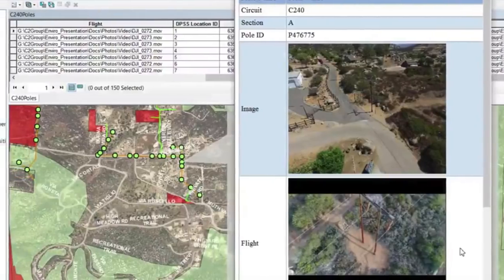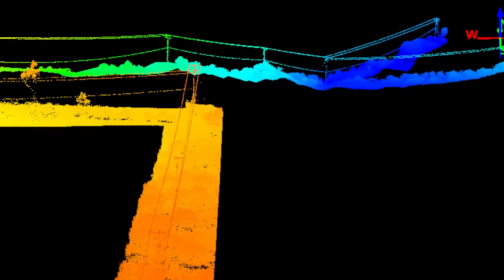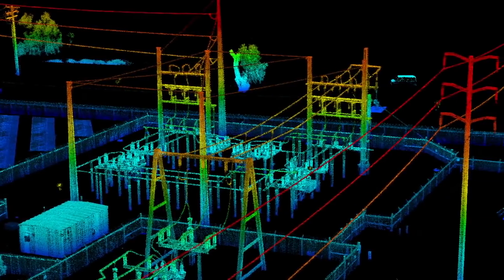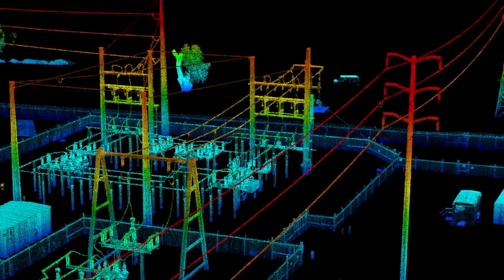And then I found out that we could go one step further, which is to embed that information within a GIS layer. Part of the FiRM program includes the as-built process, which includes doing post-construction LiDAR and identifying what the in-situ condition is. Where is our actual conductor sagged at relative to what we specified in construction? When we do quantify this, we're able to develop these PLS-CAD models, which tell us the in-situ condition and also provides us the most up-to-date information for future reference. So if anything changes in the future, then we could very quickly reference these models and change things as necessary.